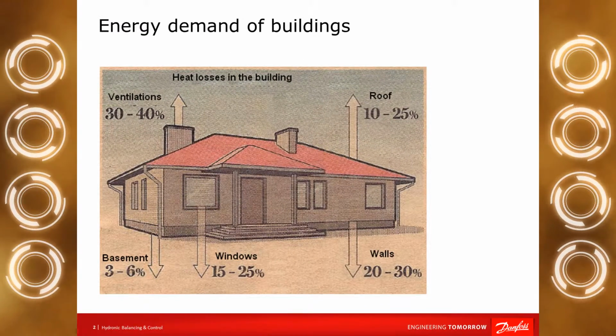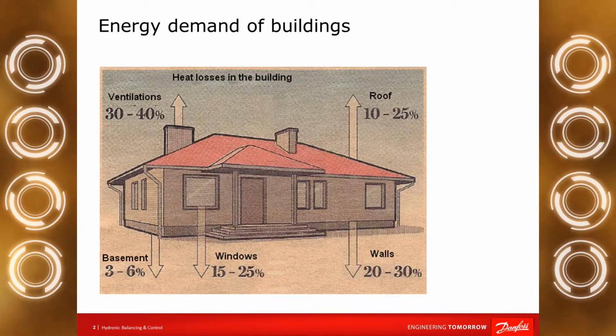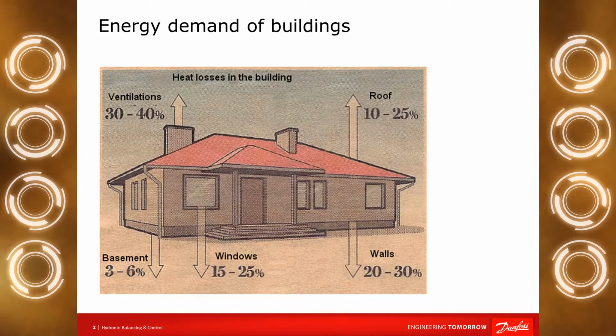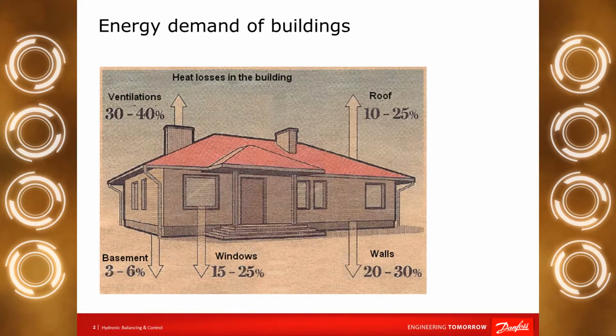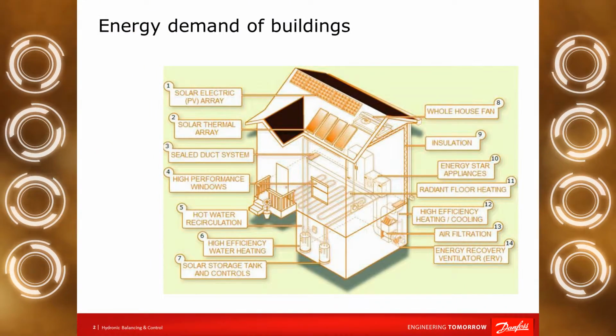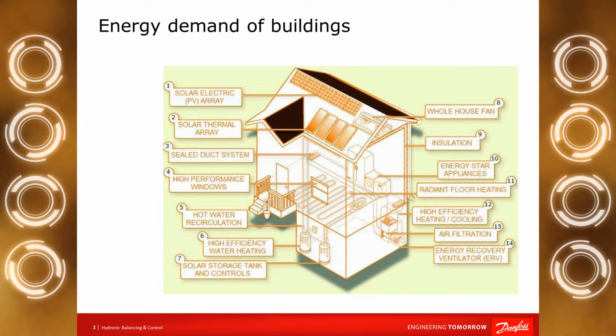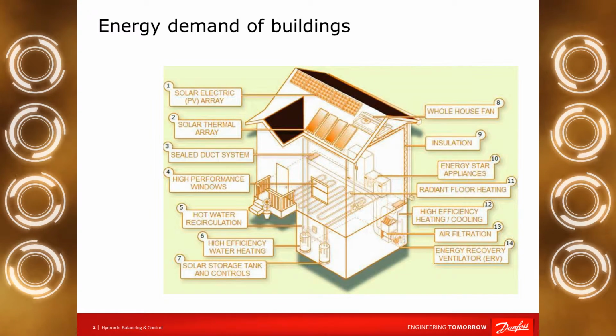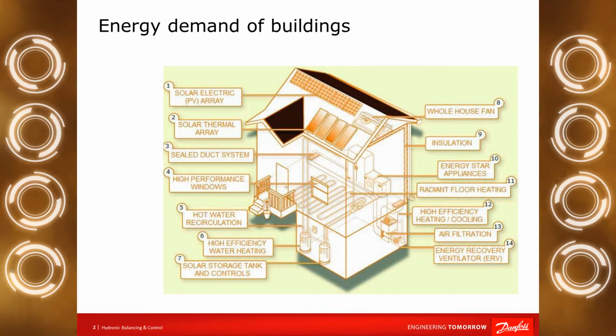When we talk about energy demand, we can see the demand depends on the insulation of the building, the windows, how much heat we lose through the chimney, etc. It's quite obvious. Everybody knows about it. If we talk about the energy saving potential, we mention many different things: for example, thermostatic radiator valves, condensing boilers, solar energy, and so on. But I have never seen a picture like the one you can see on the screen, the energy saving potential of hydronic balancing. I would like to point that out today.